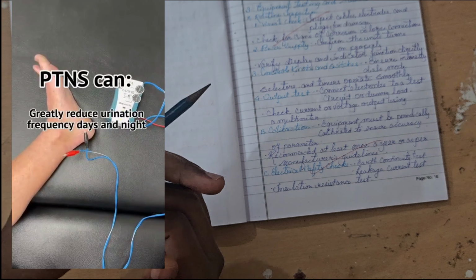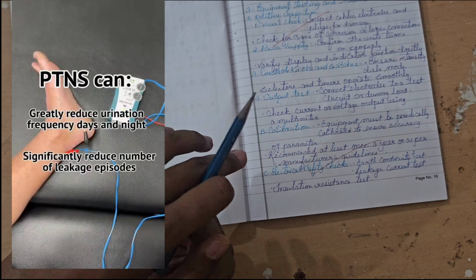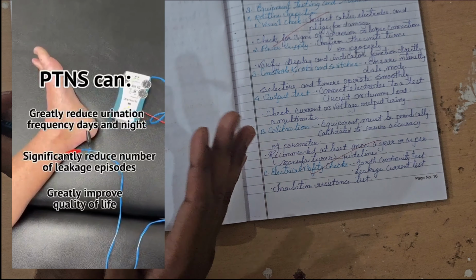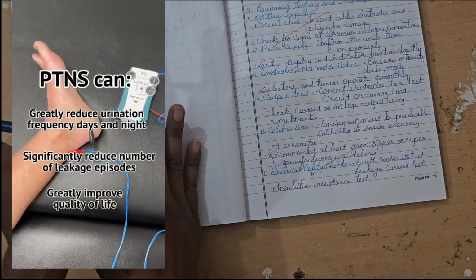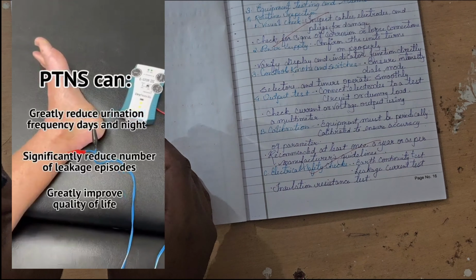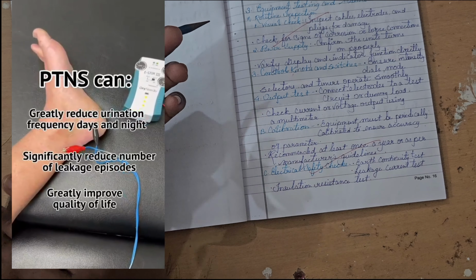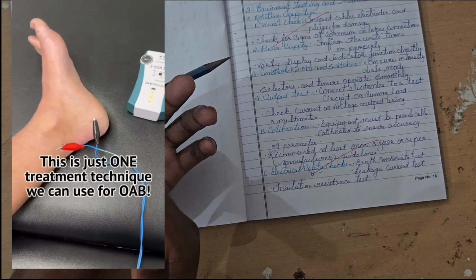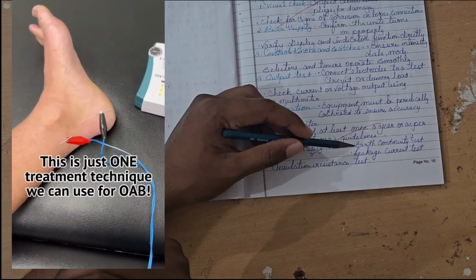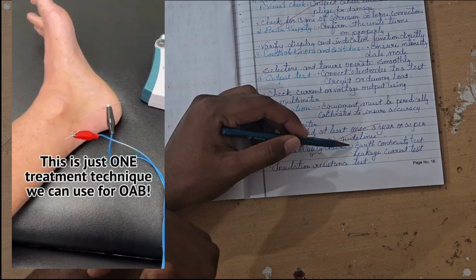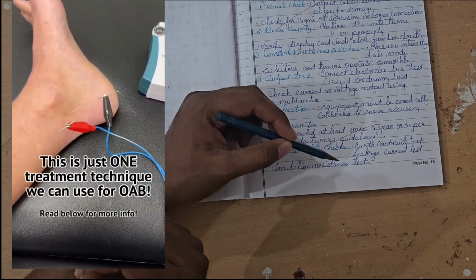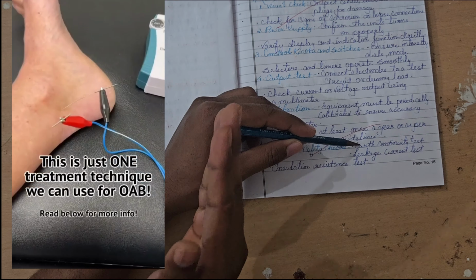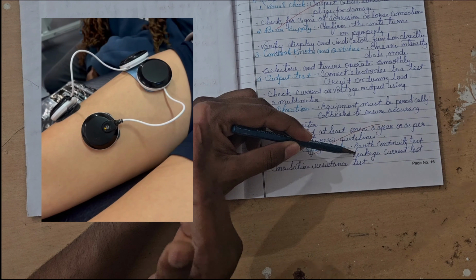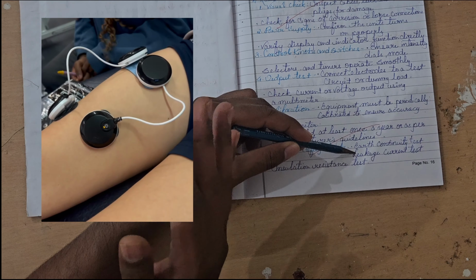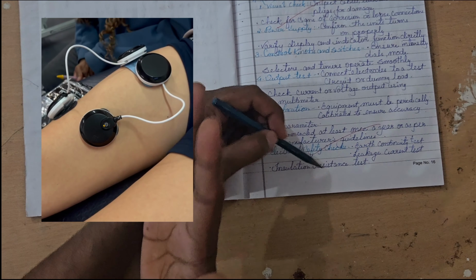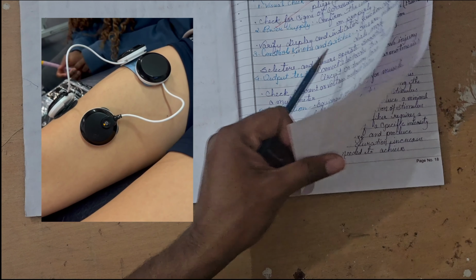Must ensure that for one year you can recheck or you can apply a new gadget, not a new machine. You can apply a new cable or different kinds of electrodes for the patient for accurate and good quality patient assessment. Electrical safety check: earth continuity test, leakage current test, and insulation resistance. So you can check whether the earthing is good or not. Leakage of the current: whether it is present or not, like any kind of cuts in the cable. Insulation resistance test: whether insulation is present or not on the machine.